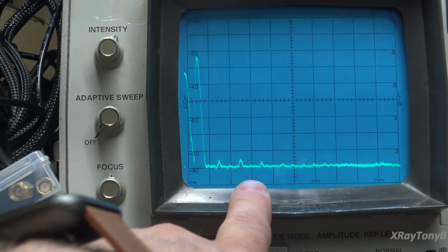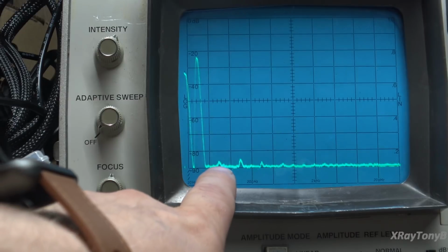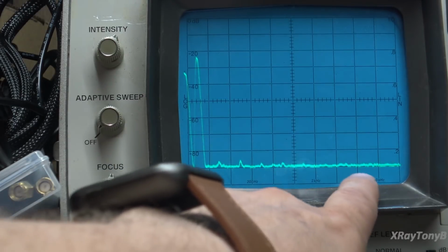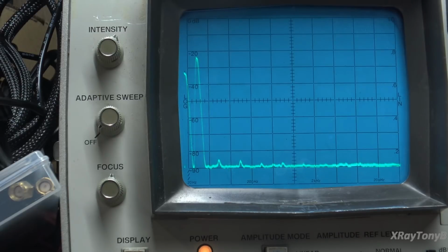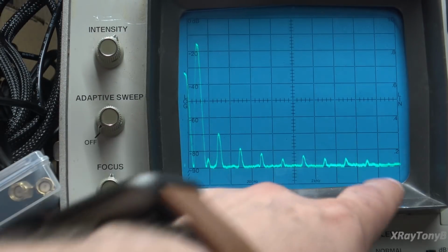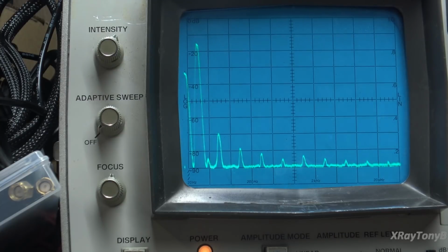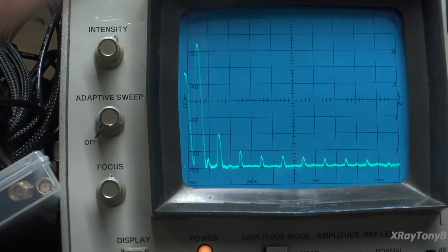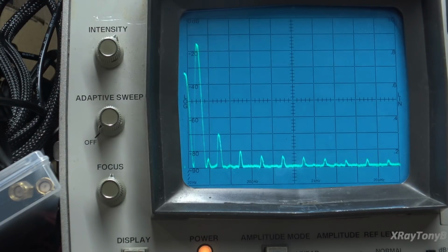If we continue up with our volume, we're now at 10 watts. And you can see at 10 watts, you just start seeing the harmonics showing up. And if we go up to 50 watts, there's some significant distortion there. So again, the THD meter and the spectrum analyzer and our MDO kind of all agree with one another. There is some kind of a problem in this amplifier. It shouldn't be like that. At least I don't believe it should be.